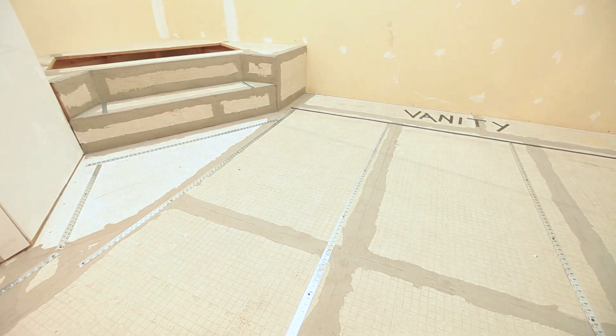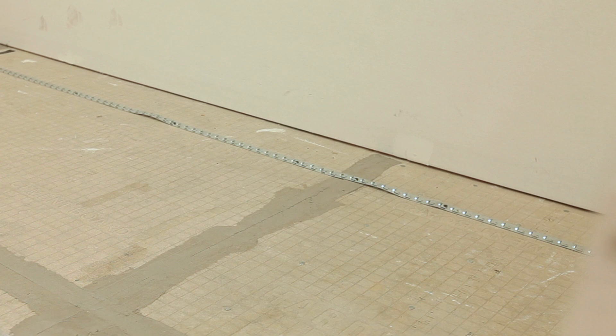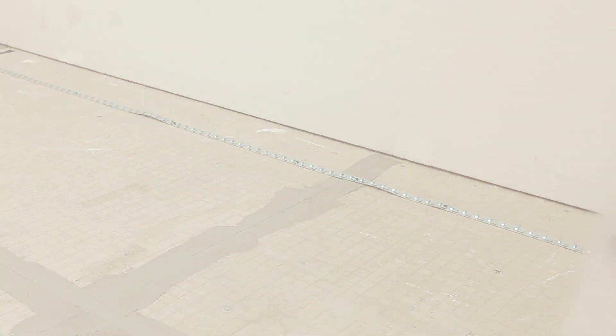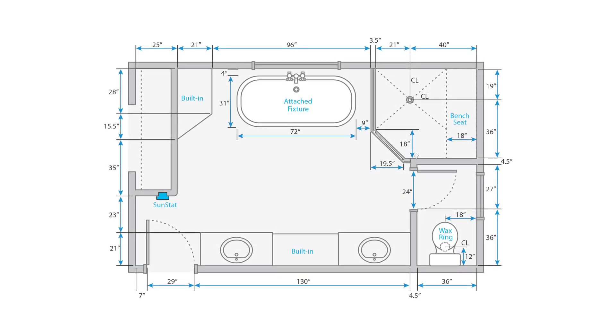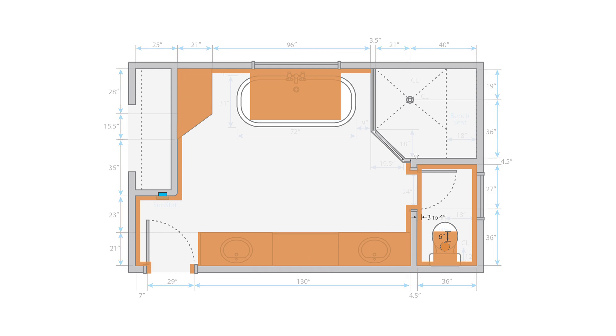Near walls where people do not stand and where trim board may be installed, place strapping 3 inches from the wall. Do not install warm wire inside closets or under built-ins.